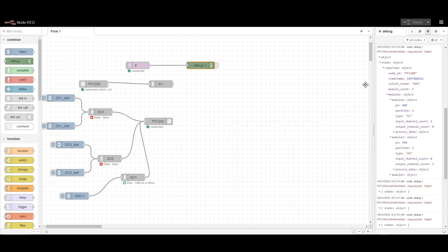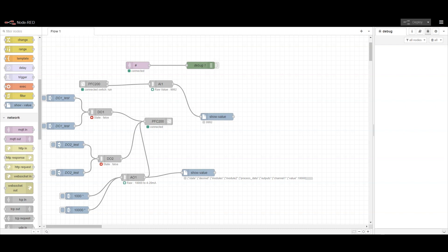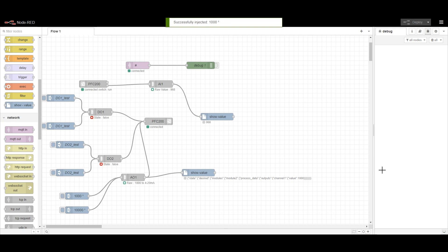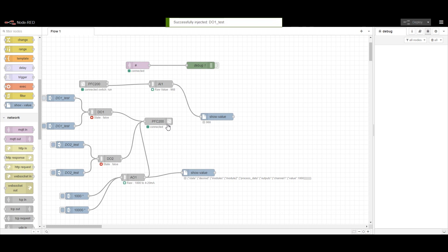I am configuring some basic logic so that when I send a command we can see the values on both the input and output side. If you see in the debug, all the different configuration details are provided. I gave a command value of 10,000 counts and I am getting 9972 on the input — and when I inject a value of 1000, the analog input card reflects a different value. In this way analog input and output can be configured very easily.